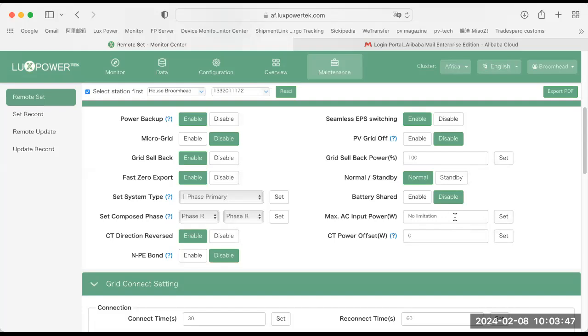This feature here is a very, very cool feature. I like it on the LXP range. It's the max input power limitation. Basically what that means is that you can set it, for instance, on an LXP5, to the size of your breaker. So if your feed breaker is a 32 amp breaker, you simply go 32 amps times 230 volts, and that will tell you what your power limitation can be here. You set it, and it'll always make sure that the AC feed to the machine, including the throughput, will never exceed this value.